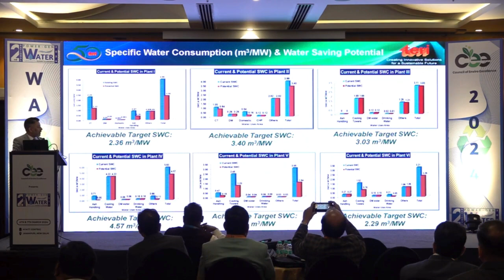For plants already using wet processes, the first thing to consider, the large low-hanging fruit, is to increase the recirculation process. The range varies significantly - some plants were at less than 10% recirculation, others already around 70%. So I can't generalize a fixed percentage as my recommendation, but most plants were not in that 70% range.